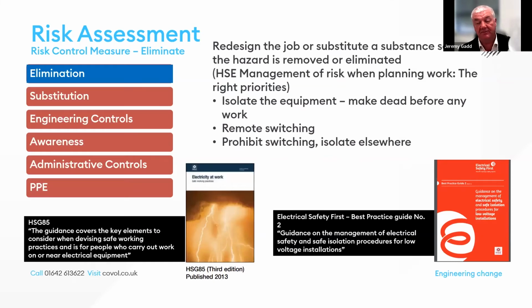So, elimination. The first approach to consider is to take away the hazard completely. Not always practical, because of the requirements in the Electricity at Work Regulations, those legal requirements with respect to working dead, and consider remote switching. And although this minimises the risk to personnel, it doesn't alleviate the risk of damage to switchgear. So in other words, you can take the person away, but if the arc flash event still occurs, you are likely to see fundamentally damaged switchgear.